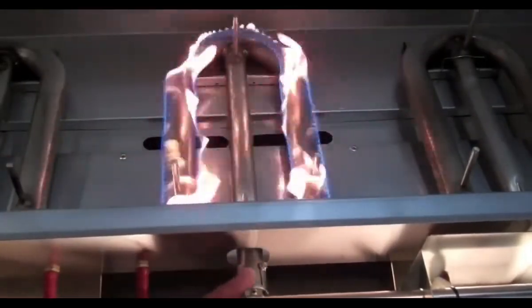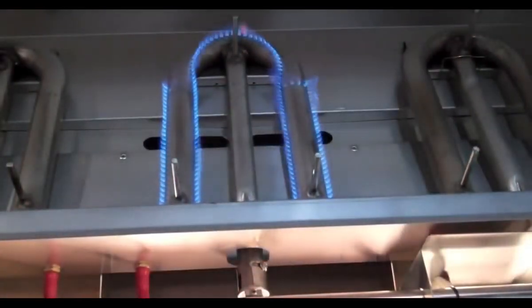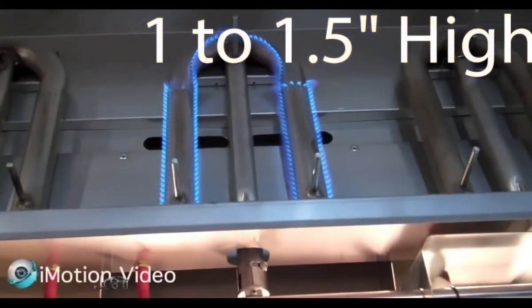With the flames burning, we want to adjust the air shutter open and closed until we have a clean, even burning blue flame that is approximately 1 to 1.5 inches high.